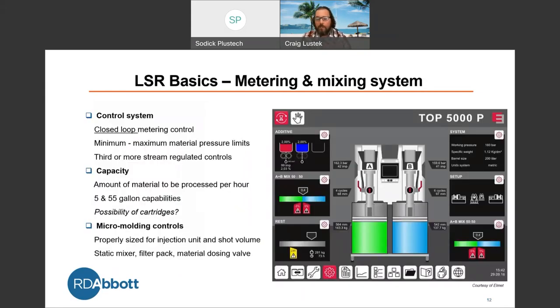And I talked before about a control system, a closed loop. And that closed loop system we're looking for is the metering control. This screenshot shows an overview of that control, where you're looking at the A and B mix ratio, making sure we're staying 1 to 1. Our working pressure, how much material is left, as well as you can see on the screen, we have impulses between the A and the B, making sure that ratio is staying 1 to 1.